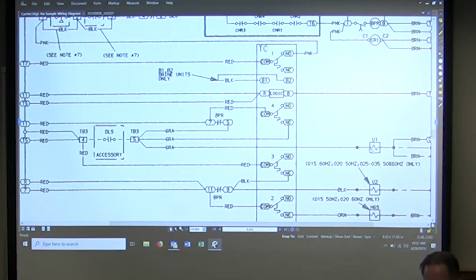So an unloader, you may not know, air conditioning, but an unloader keeps a compressor from running at full capacity, right? It's unloading it. It'll take half of the pistons out of the circuit, or one whole compressor. It could do different things. So it's going to basically lower the amount of energy being used. So that's what a demand limit is like. If my demand for electricity is so high that I have to start shedding some of my loads, then I would energize that. So having a solid line here would never let this load up to full capacity. So if we put in a demand limit, it's got to be a switched contact, like it shows there.